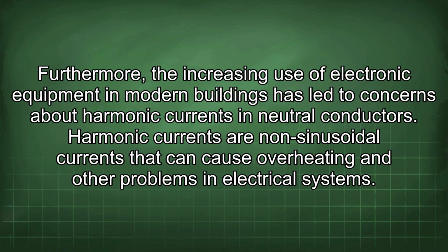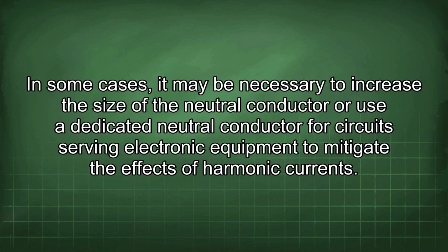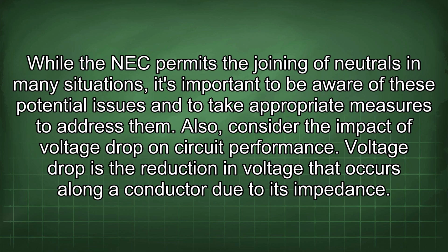Furthermore, the increasing use of electronic equipment in modern buildings has led to concerns about harmonic currents in neutral conductors. Harmonic currents are non-sinusoidal currents that can cause overheating and other problems in electrical systems. In some cases, it may be necessary to increase the size of the neutral conductor or use a dedicated neutral conductor for circuits serving electronic equipment to mitigate the effects of harmonic currents. While the NEC permits the joining of neutrals in many situations, it's important to be aware of these potential issues and to take appropriate measures to address them.